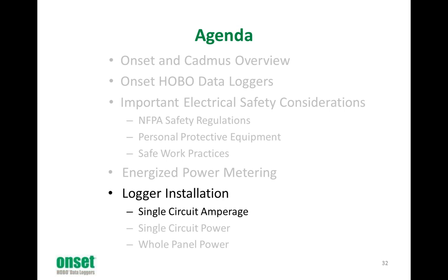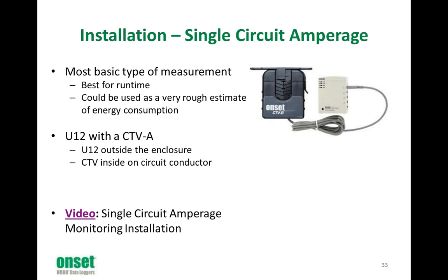So now we will look into single circuit amperage and how to log that. For this installation, we're going to use a U12 with a CTVA. This method is best to capture runtime. It could be used as a very rough estimate on energy consumption, but really we're just logging amps. So again, the best way would be runtime, and it's a nice compact installation. Typically the U12 will be outside of the enclosure, and the CTV will be mounted inside the enclosure on the circuit conductor. So we'll show a short video on how we install that.